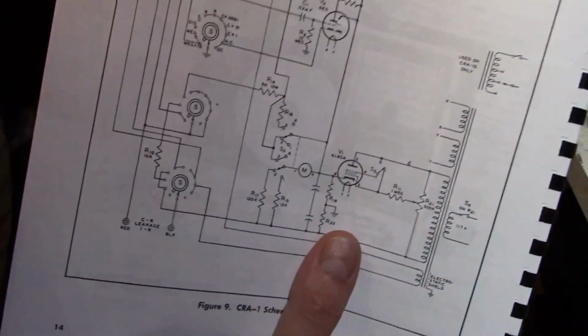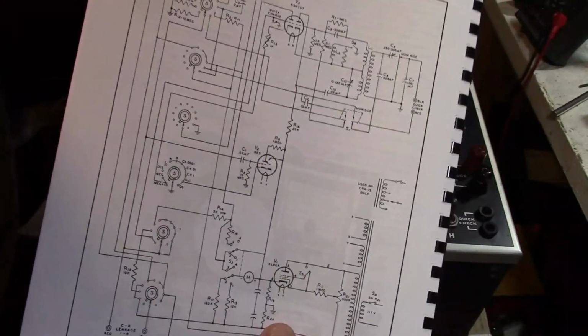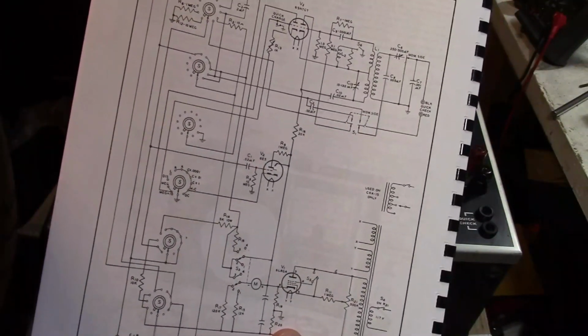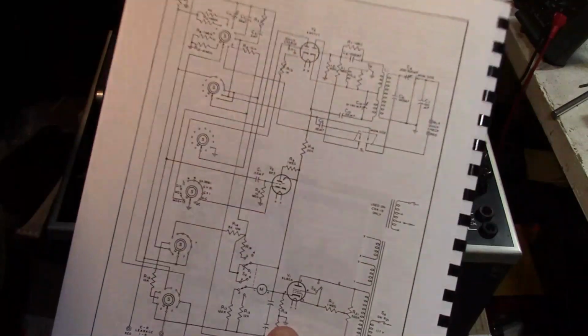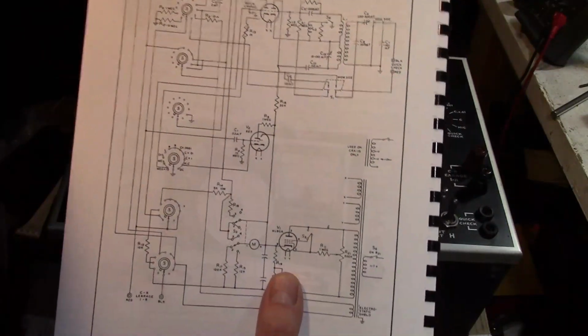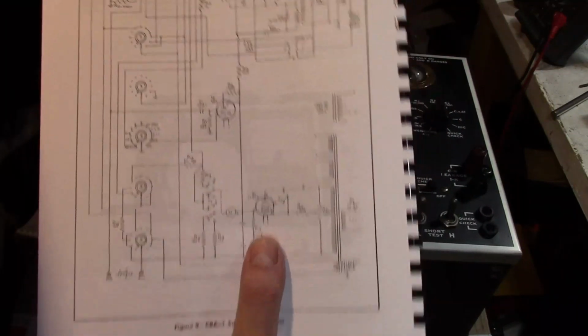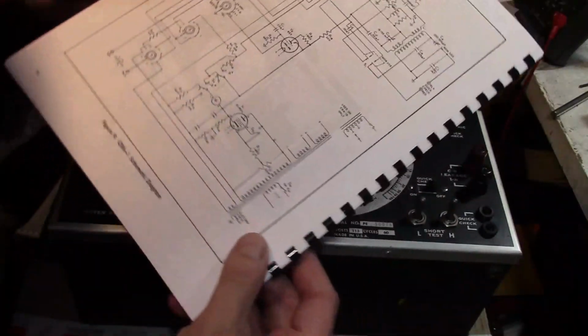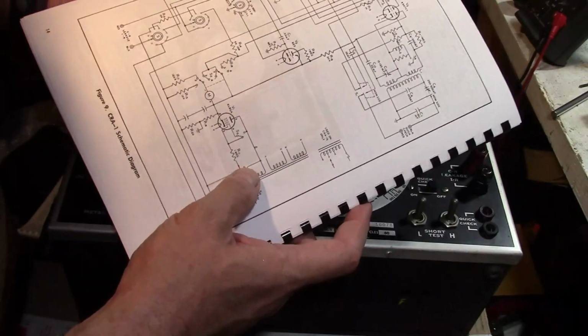I'd have to check the meter. I mean, that could be a very useful thing. If you want to check leakage current in a cap and that cap is dead shorted, you don't want to damage your instrument. So by having a tube in there that is self-limiting with how much current can go through, you can avoid burning out the meter or power transformer. That might be why they use it.